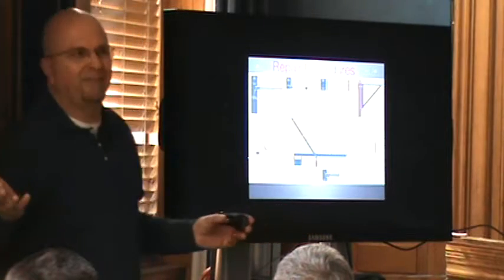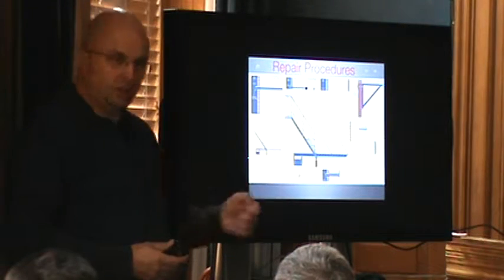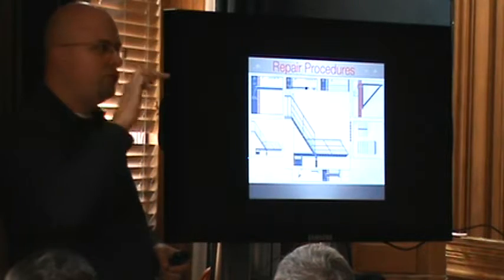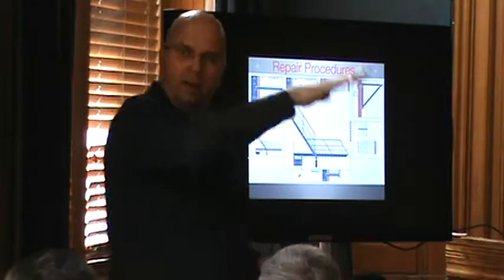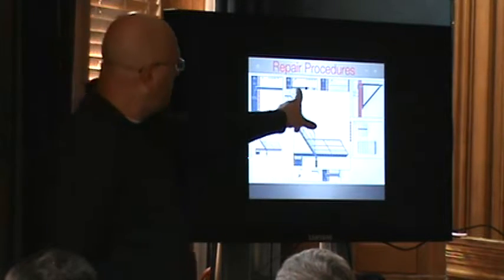No, well, I have to tell you, because you didn't know what the chain was for. You thought it was part of the requirement. It's not. Because as soon as you cut that chain, you know what that cantilever does? Now, somebody needs to get down that fire escape. How many treads do they walk out, 2, 4, 6, 8, before their weight counteracts? So this is a properly functioning fire escape. And you're talking about one that has no release arm.